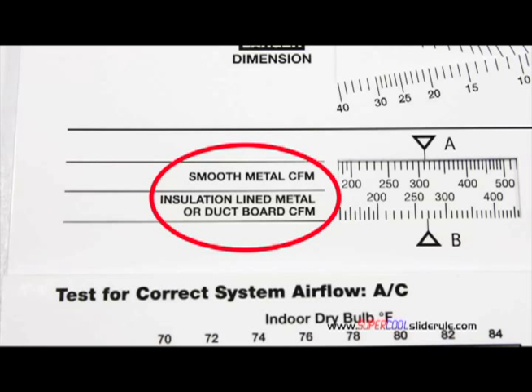The majority of technicians have never been taught that if the insulation is on the inside of the ductwork you cannot size it with a regular duct calculator.